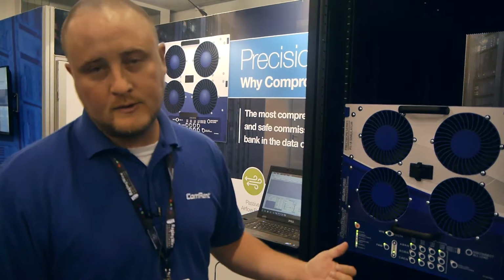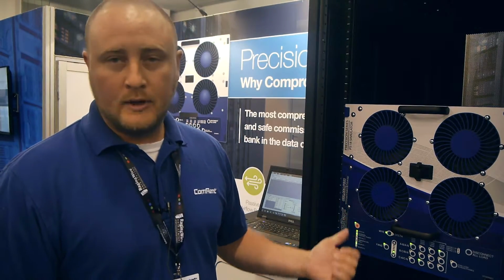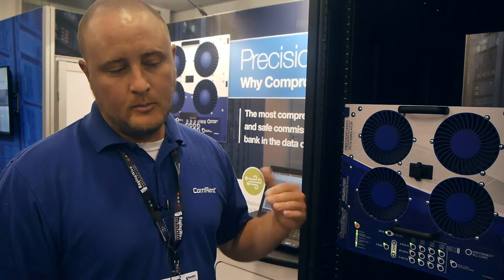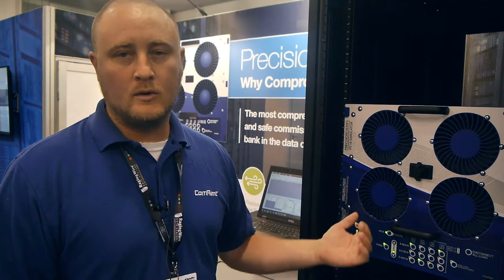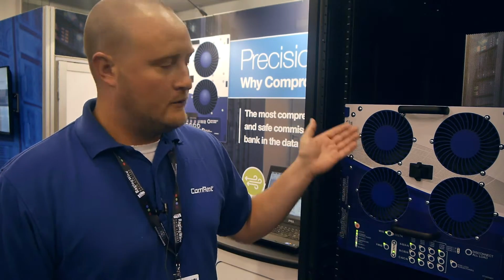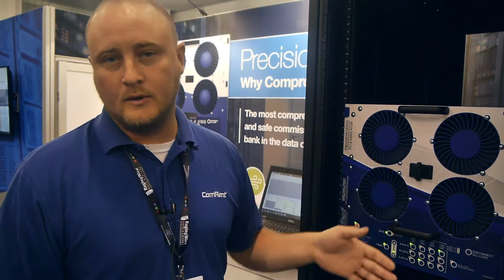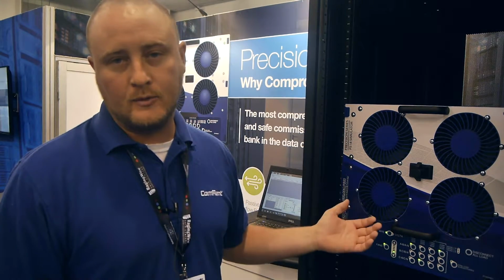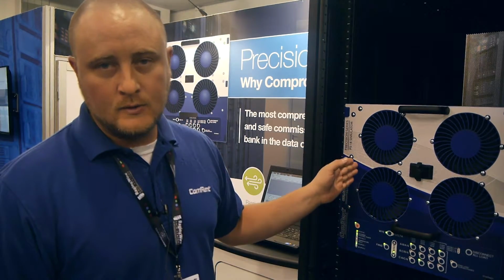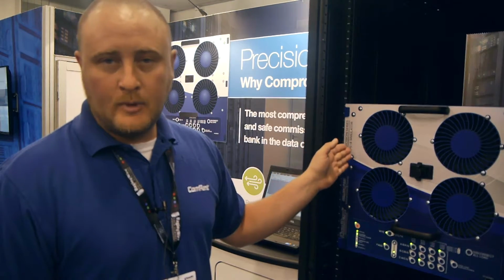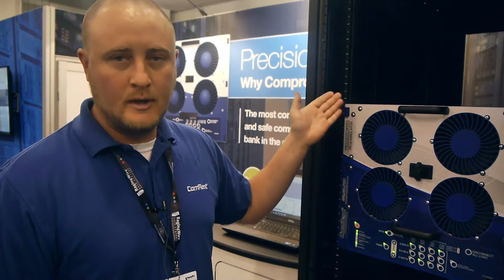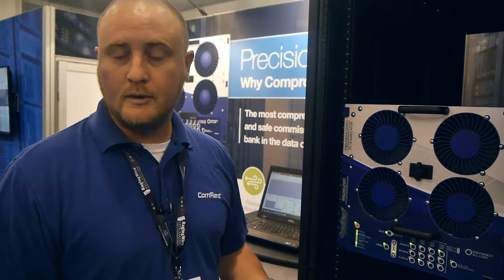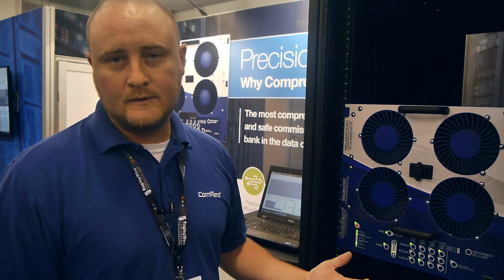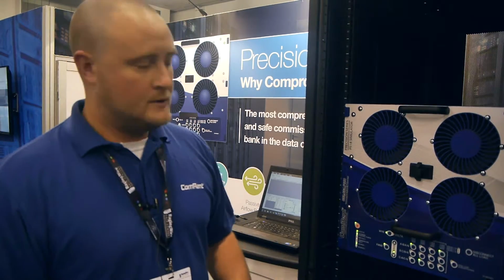The other key feature of this unit is auto transfer capability, the ability for the commissioning agent, owner, or user to fail over one source and switch to a redundant source, which in the past was not possible with a rack mount. This system allows you to fail source 1 power on a PDU or A plug strip and automatically transfer to B. You can force that through software, or set the unit up to sense it automatically. So that's a great feature.